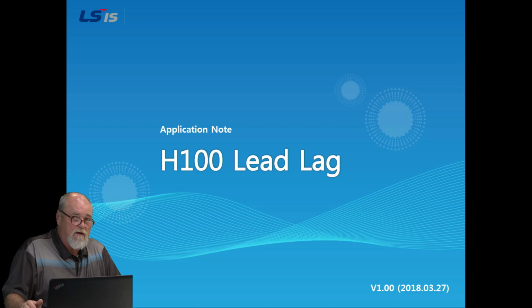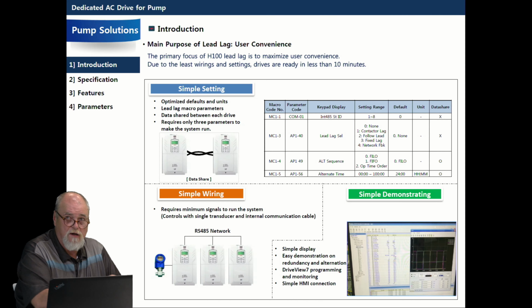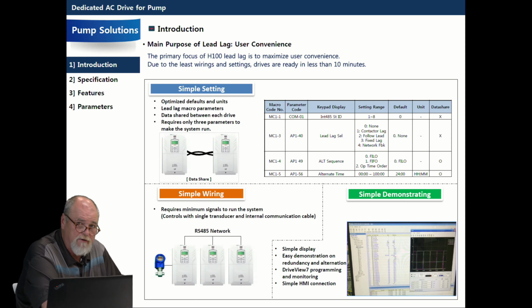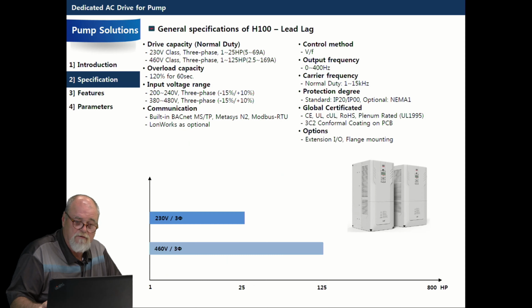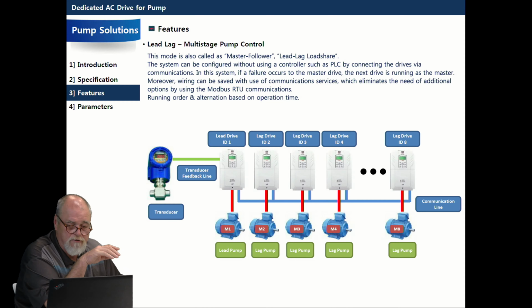We now have firmware which allows the H100 to operate in a lead-lag scenario, communicating through RS-485 networks up to 8 drives. This means we can program it to save the customer money on pumps by reducing wear and tear, programming up to 8 of them in a multi-stage setup.